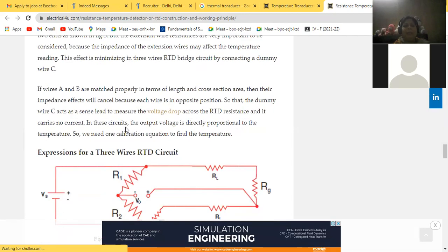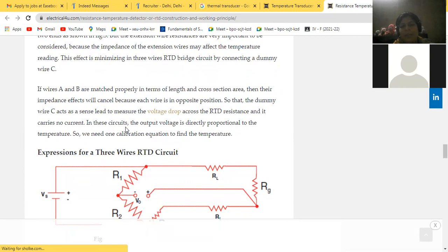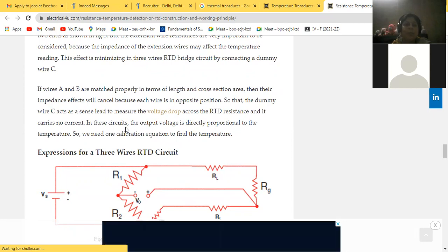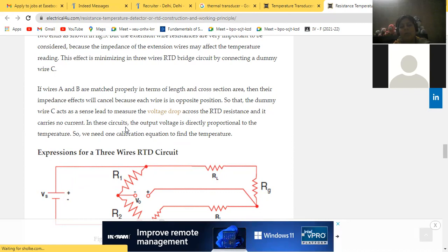Now if A and B are matched properly in terms of length and cross section area, then their impedance effects will cancel because each wire is in the opposite position, so that the dummy wire C acts as a sense lead to measure the voltage drop across the RTD resistance, and it carries no current. Now in these circuits, the output voltage is directly proportional to just temperature. So we need one calibration equation to find the temperature. Clear? Now ये अब हम कल करेंगे expression.